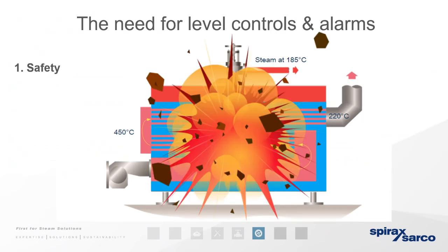As it shows here, we need level controls and alarms to make sure it doesn't explode. Of course, a sudden release of the energy would be catastrophic. Fortunately, modern day boilers have a number of different safety mechanisms to prevent this from happening, which means catastrophic incidents are very rare. In areas where water treatment is not so considered, obviously it's more common, but globally it's still a rare occasion. But it does remind us of the importance of looking after the boiler house, doing our risk assessments and making sure our boiler is running as efficiently as possible.